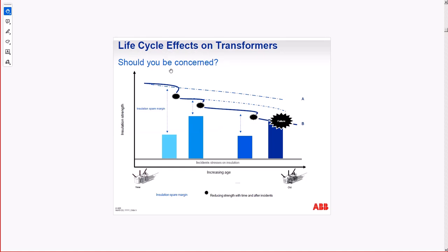Life cycle effects on transformers. We have here incident stress of the insulation. So as the stress increases in strength, we actually derate the insulation, and the insulation is closer to a complete failure. New transformer on the left, old transformer on the right, and that's with the increase in age. You see at the beginning the transformer is able to sustain those kinds of faults without having a final failure, but as the transformer ages, that margin disappears, and the same failure that was still supported by the transformer at the beginning will, when it's old, just destroy the transformer with a final failure. Same with us. So it's very much an analogy with people in many regards. You're going to see that on the slides.